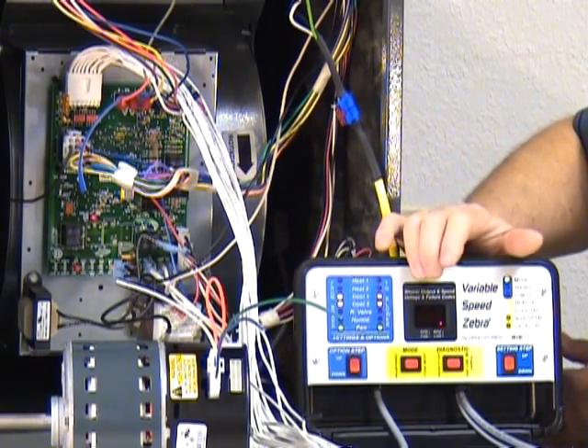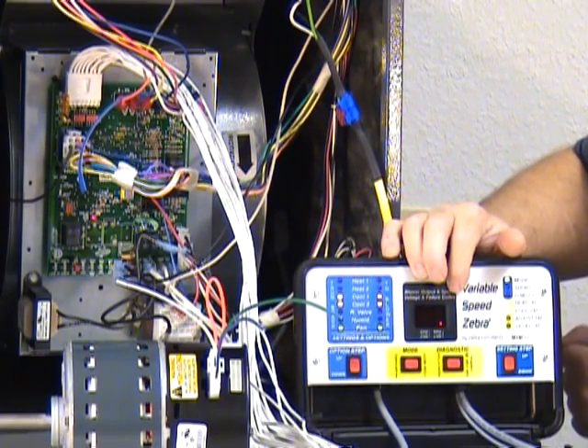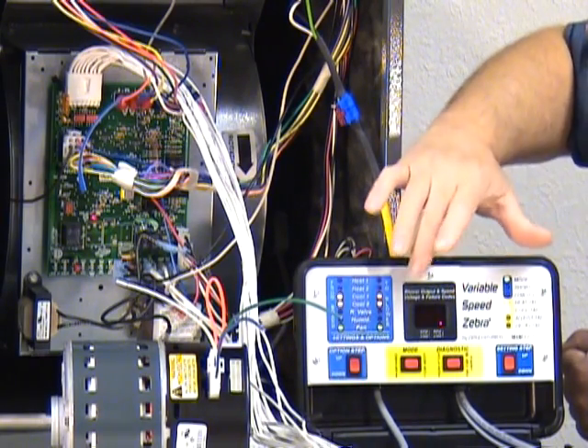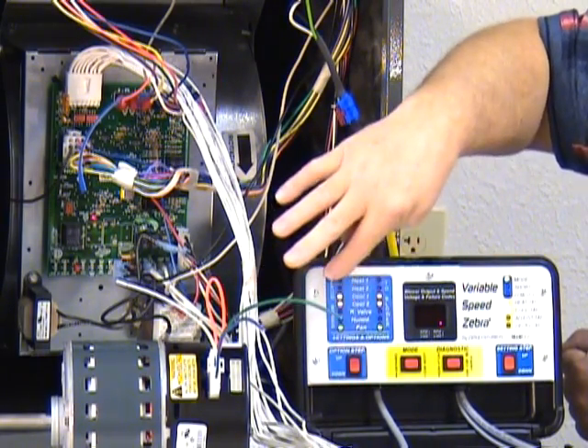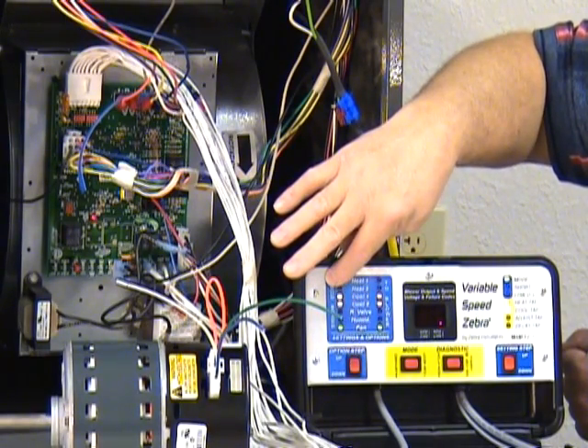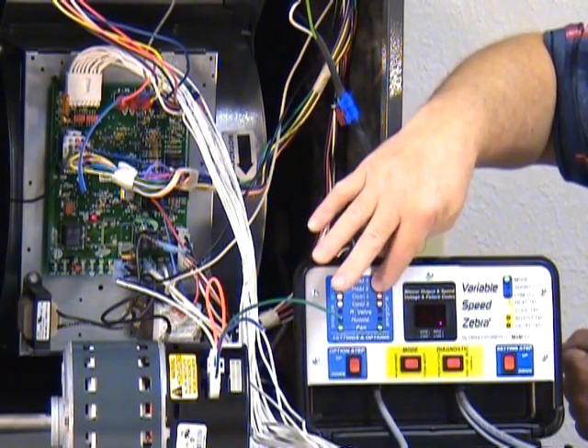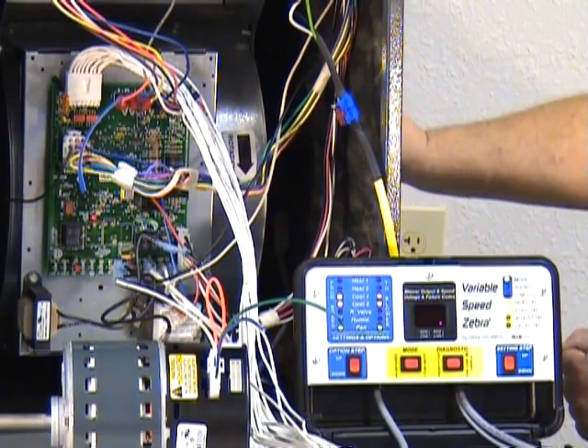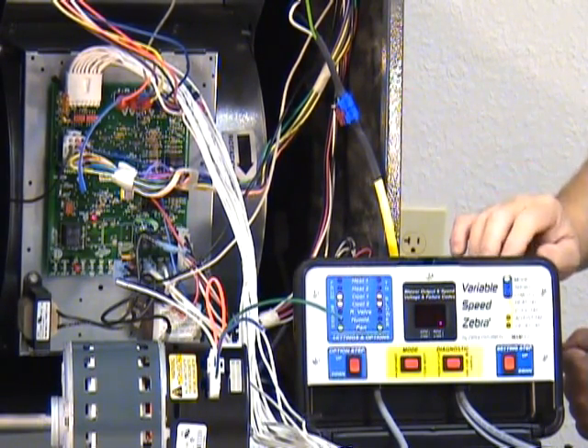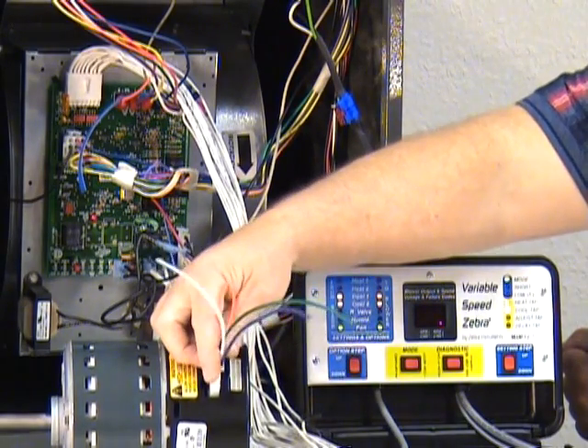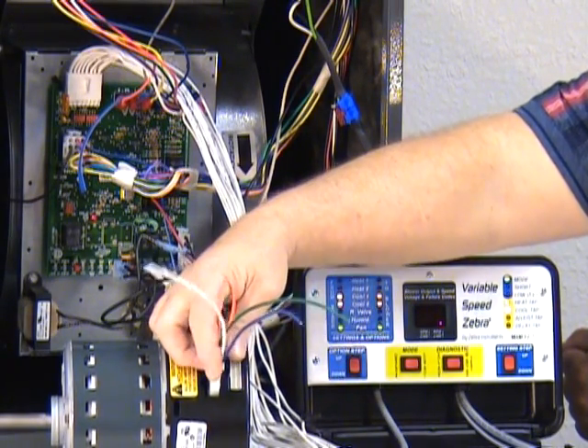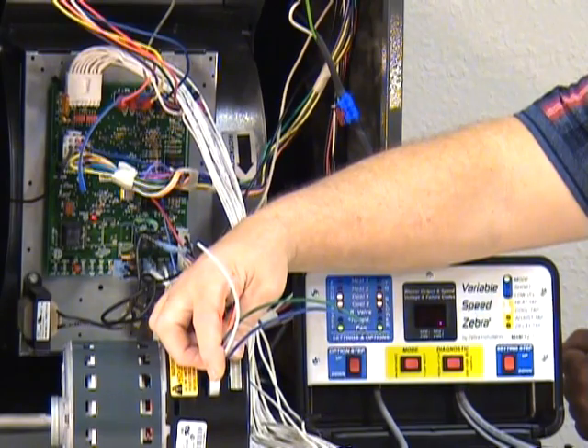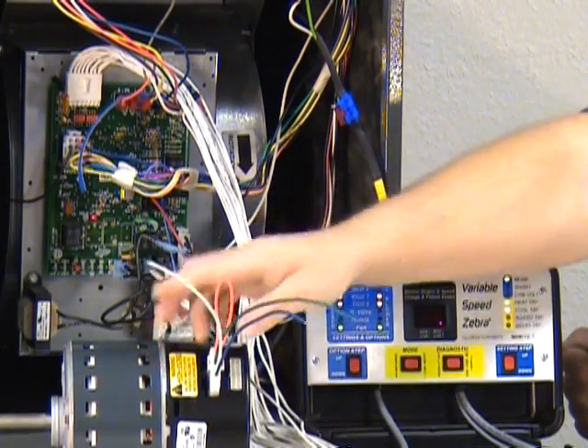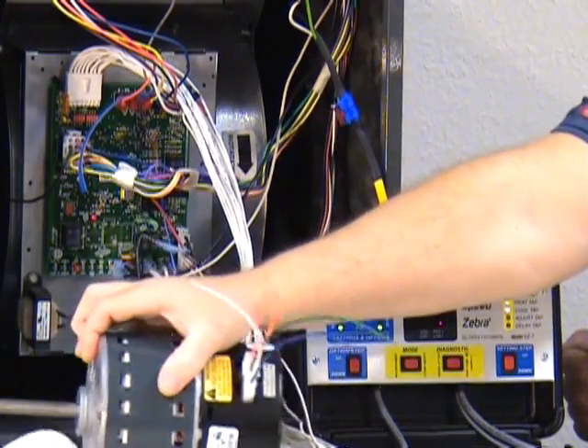Again, the variable speed Zebra's main purpose is to help you diagnose what's wrong with the system or to help you set it up originally. So what you're going to be doing is observing what's happening here with what's happening here, and then watching to see what the motor does in response. If it doesn't work, you're going to check the power coming into the motor like you did with these power connectors. If you haven't got any voltage coming in here, one thing I might point out, let's zoom in on this side if you can see it.